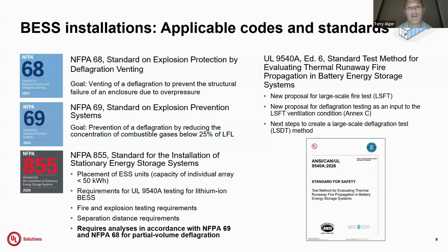NFPA 855 requires 9540A testing for lithium-ion battery energy storage systems, which I'll talk about in a minute. There are some fire and explosion testing requirements, and 855 requires analysis in accordance with NFPA 68 and 69 for these partial volume deflagrations. The test method many of you have probably heard about, UL 9540A, has just come out in its 6th edition. It's got a new proposal for a large-scale fire test, which has been demanded by the industry for some time now. We're also working on a new proposal for deflagration testing as an input to the ventilation condition. So, taken all together, this test method and these standards serve as a set of guidelines and rules that attempt to reduce the risk from these battery energy storage systems.